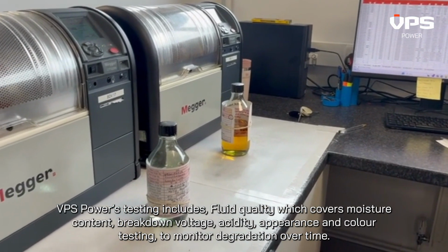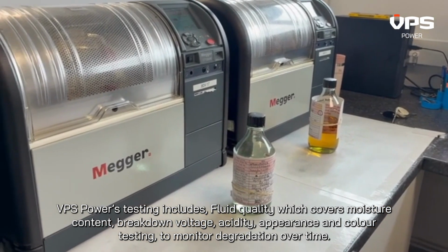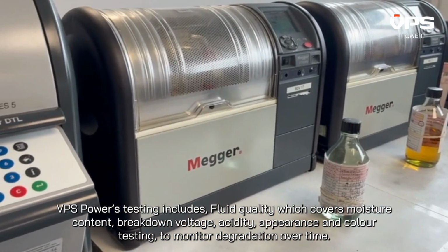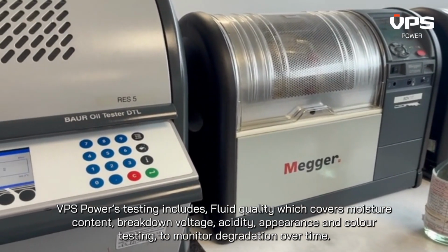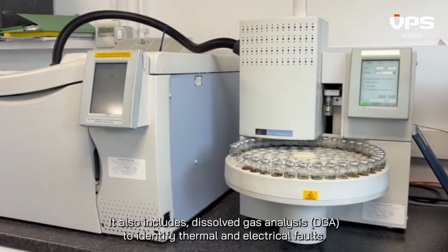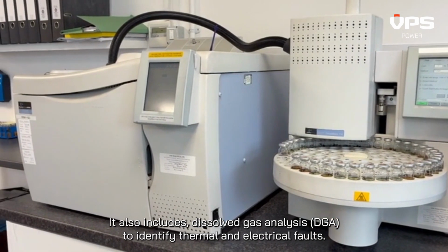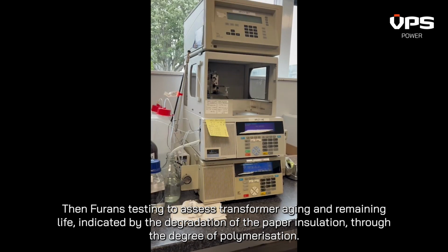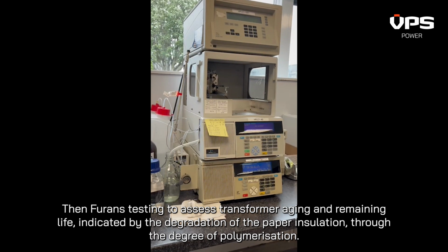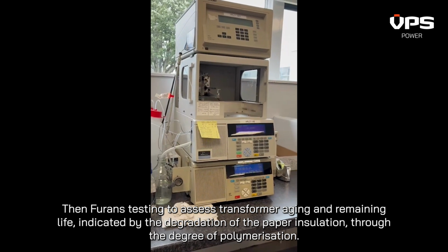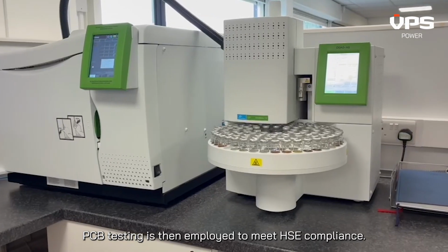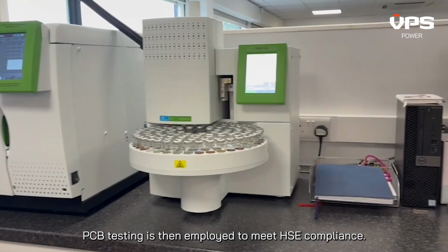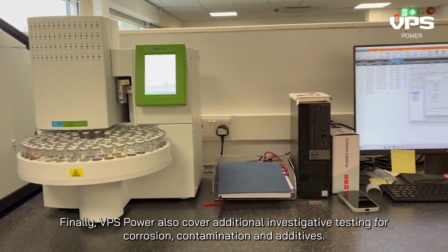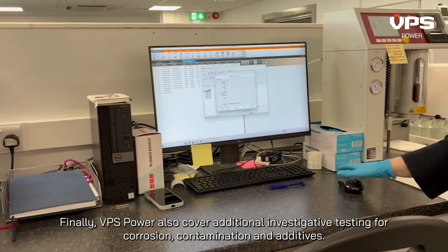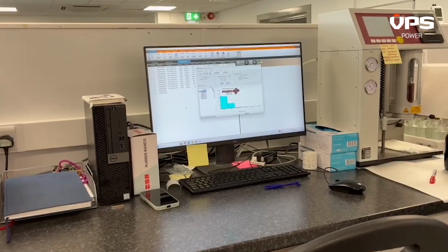VPS Power's testing includes fluid quality, which covers moisture content, breakdown voltage, acidity, appearance, and color testing to monitor degradation over time. It also includes dissolved gas analysis, or DGA, to identify thermal and electrical faults. Then furans testing to assess transformer aging and remaining life, indicated by the degradation of the paper insulation through the degree of polymerization. PCB testing is then employed to meet HSE compliance. Finally, VPS Power also cover additional investigative testing for corrosion, contamination, and additives.